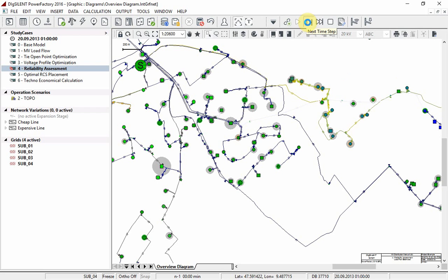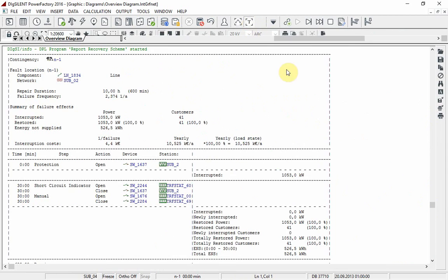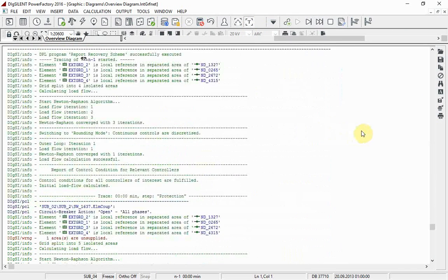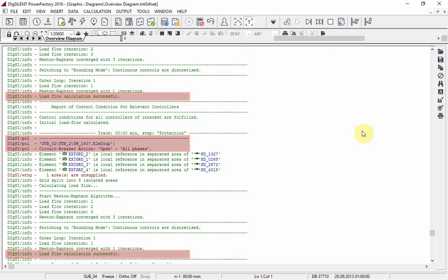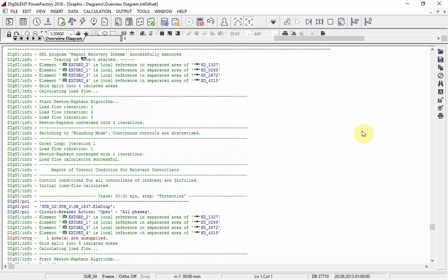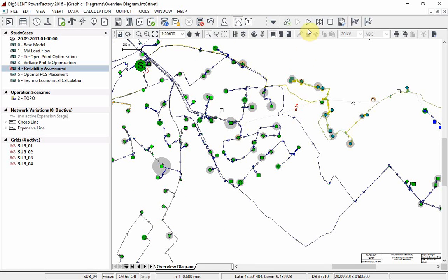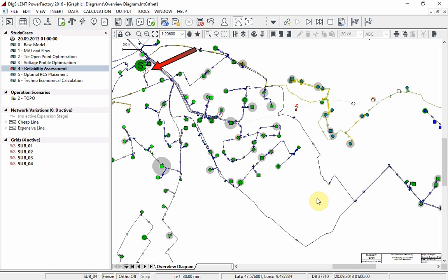A fault is applied to the line and it can be seen that the circuit breaker at the substation opens. In the output window you can also follow the steps. Move to the next step of the trace. You can see that switches at both ends of the faulted line have opened. You can also see that the circuit breaker at this substation has closed.